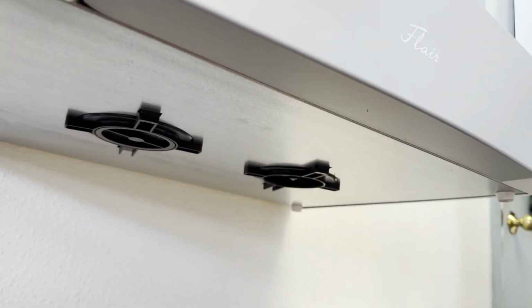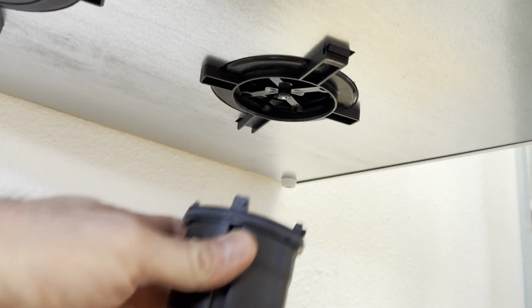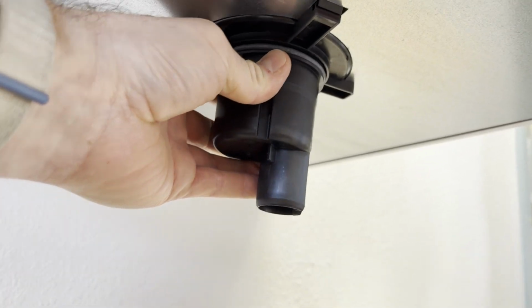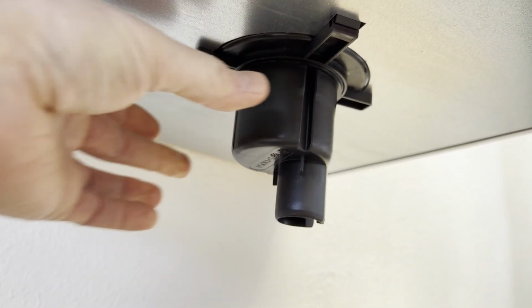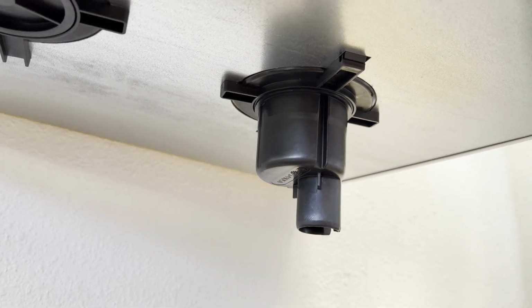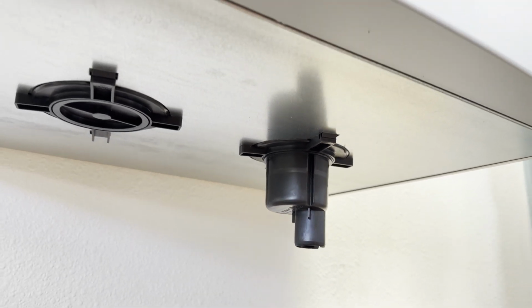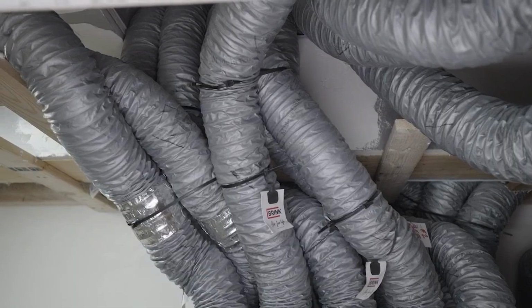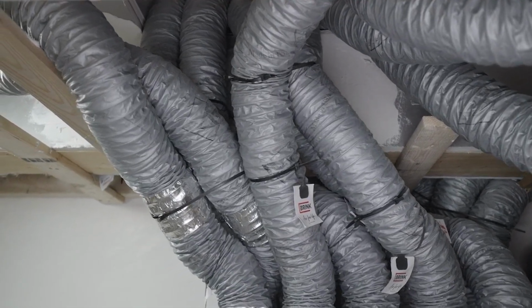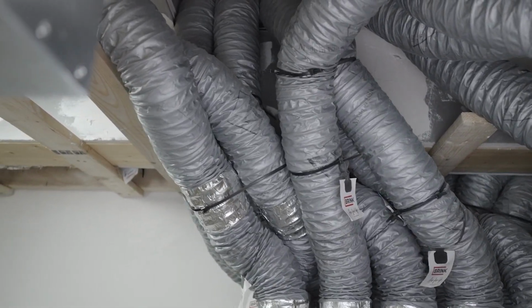For HRVs, you should look for the P-trap and condensate line and ensure that this has been installed on the correct port at the bottom of the unit. ERVs do not require a condensate line. Next, check that the ductwork is installed correctly for the unit's orientation.